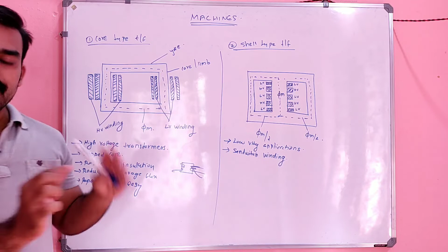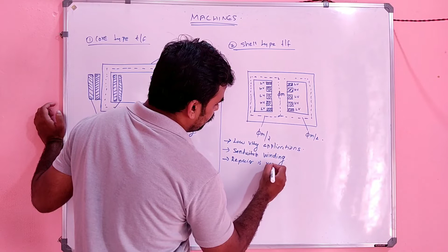So sandwich winding is used here, and the problem with this type of winding is that repair is very difficult. Repair is very difficult because if anything happens inside the coil, the whole transformer has to be broken in order to get the windings outside. So repairing of the shell type transformer is very difficult when compared to the core type transformer. Once it is damaged, it is simply damaged. We don't try to repair that. It is very easy to remove it and buy a new transformer. That much difficult is the repairing.